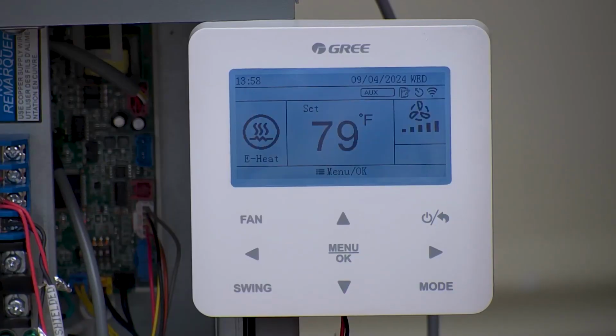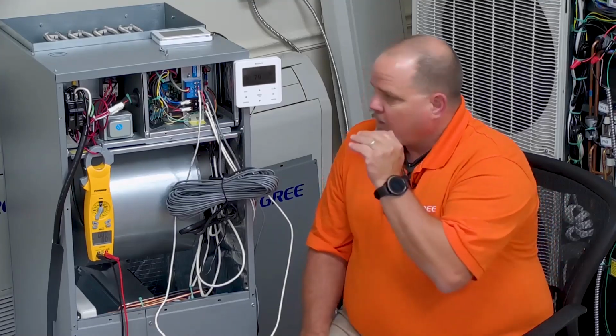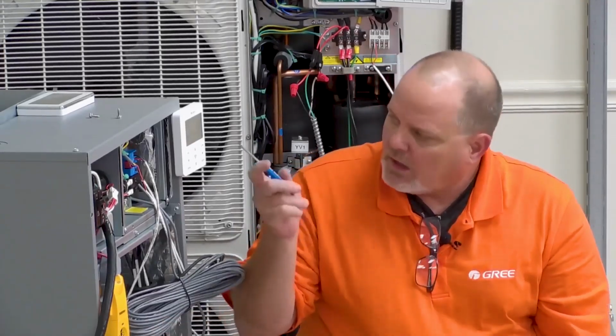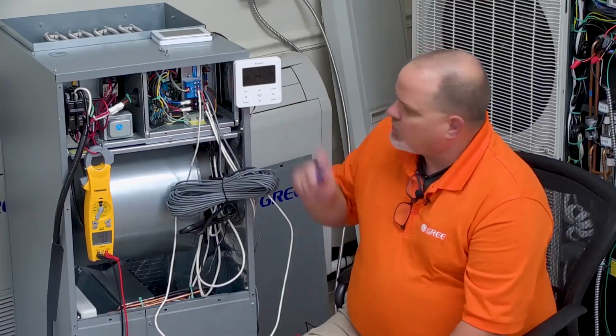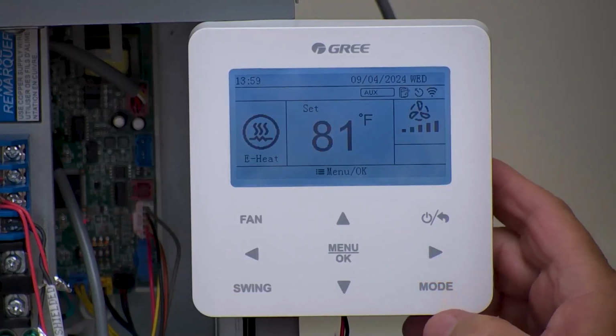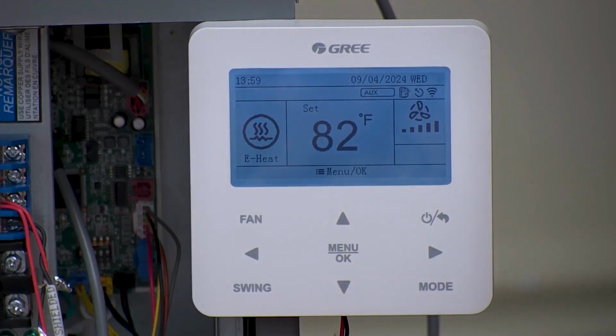So the other thing that we gained while we're waiting on that for a minute, the other thing we gained with this, and I've tested this myself, even if I lose power to my outdoor unit, which normally would give you a communication error code, and you lose all function of the GREE MultiPro unit. You will lose all function to the GREE MultiPro unit. But as long as that blower motor can still work and the board is still good, you will still have eHeat function. Again, it might be because I cycled it so quick. It's probably got a delay in it. But we'll give it a minute, see if it don't kick back in here. And then I also want to demonstrate that it'll work with the power off. I'll just kill the power to the outdoor unit.